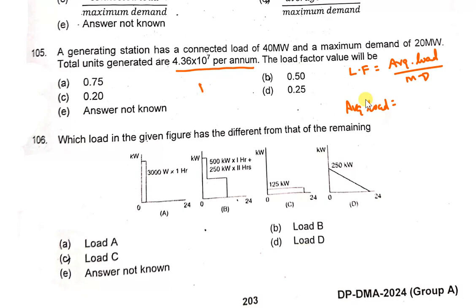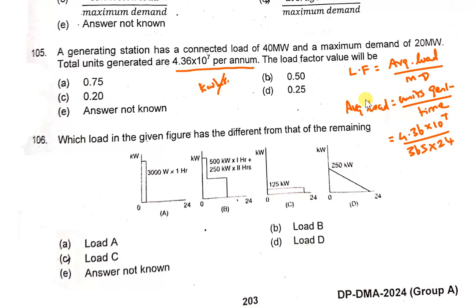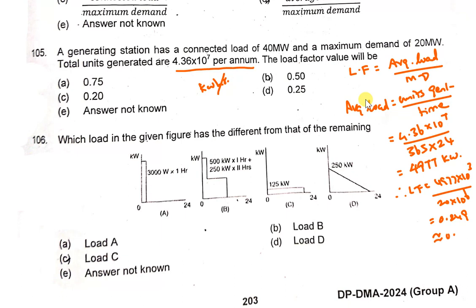Units generated per annum divided by 365 days × 24 hours gives an average load of approximately 4977 kilowatt. Therefore, load factor = 4977 × 10³ divided by maximum demand of 20 × 10⁶, which gives approximately 0.249, so we take 0.25.